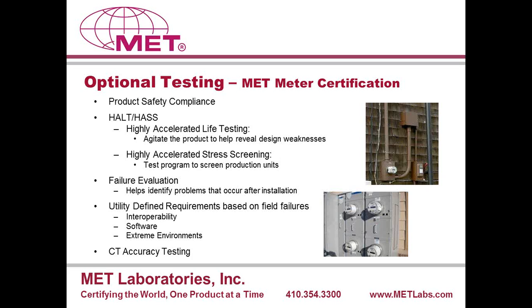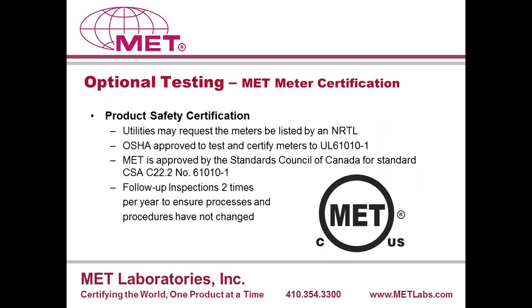Failure evaluation, I just touched on it. Identifying any problems in the field. Many times the manufacturers or utility will continually see problems. Any product can fail. But when you start seeing reoccurring problems that are accumulating, and it's tough to sort of nail down exactly what may be happening, that can certainly help you try to develop a test program within the laboratory, a controlled environment, to help bring out that failure and try to get to a determination of what, in fact, may be causing that. And, of course, this many times is well beyond what's required by ANSI. Utility or manufacturer-defined requirements. I mentioned our customer-specific test programs. That would fall along those lines, where we can, again, develop a test program specifically for what you're trying to target. We also have a CT accuracy testing capability here, so we'll get into all these here.